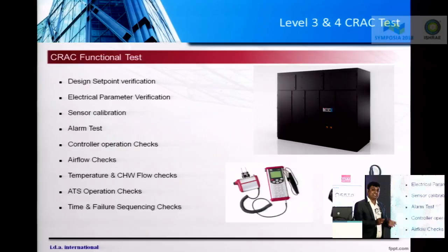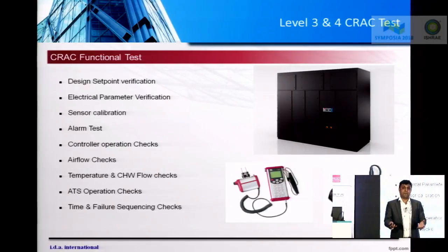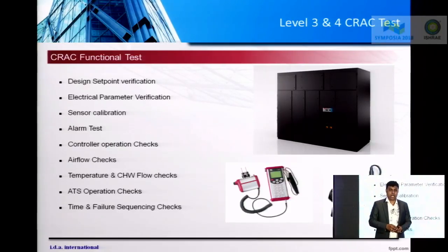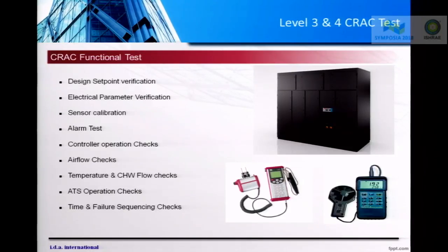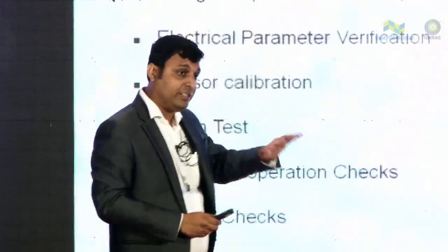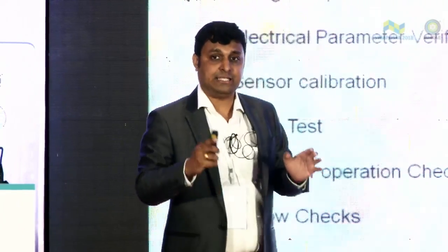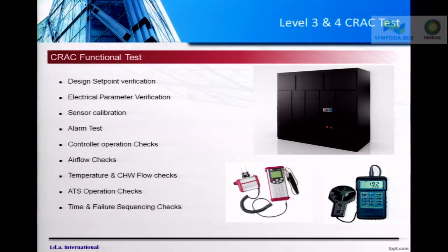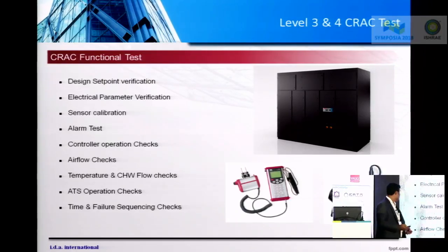Then comes sensor calibration. You have many sensors, right? In data centers, you could have multiple supply air temperature sensors. You have return temperature and humidity sensors. You have to ensure that those sensors are giving you right readings, right? The tolerance limit should be plus minus 0.5 or 1 degree Celsius maximum. If the tolerance limit is more than that, it means the sensors have to be calibrated again. Then comes the alarm verification. You have to verify the alarms.